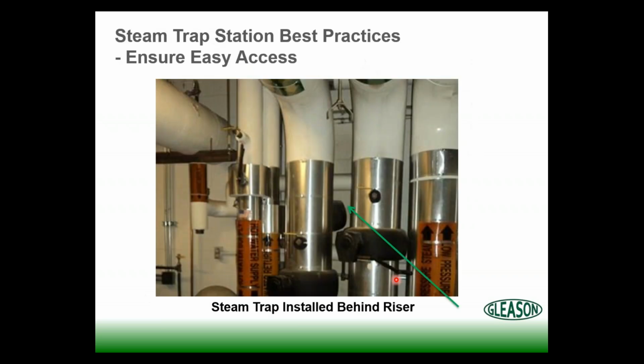Another steam trap station best practice: let's make sure we can get to the steam traps. This was something we ran across in the last few months where they did a beautiful installation of the steam trap, but if anybody ever has to service it, they're not going to be able to. And if you can't get to it, you're not going to check it, you're not going to service it, and other problems can arise from that.